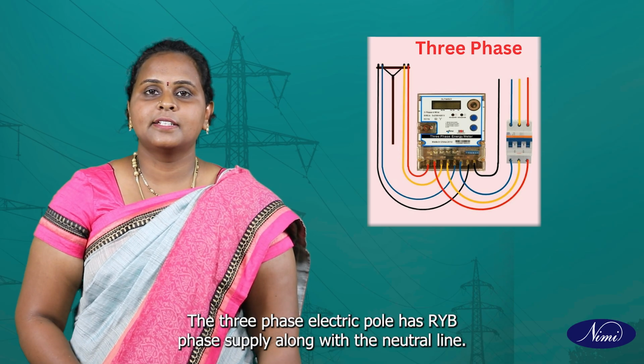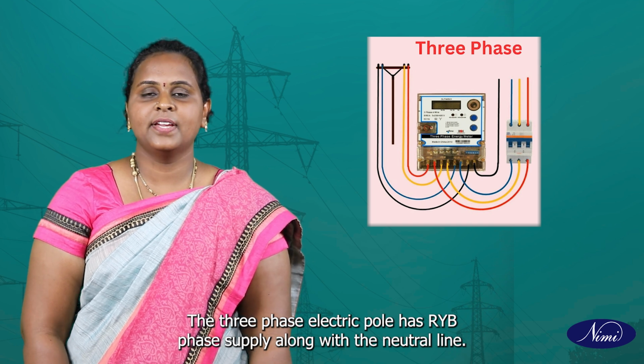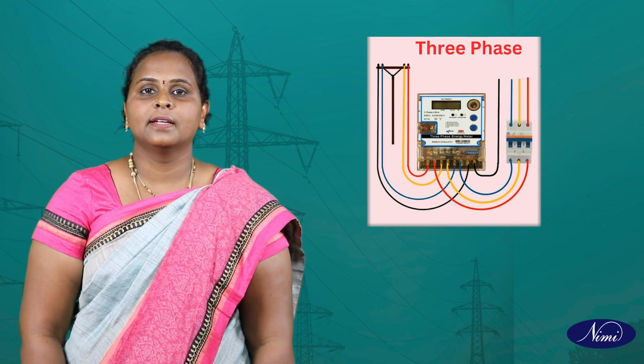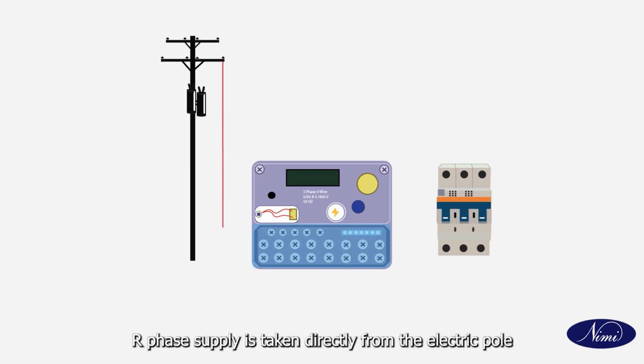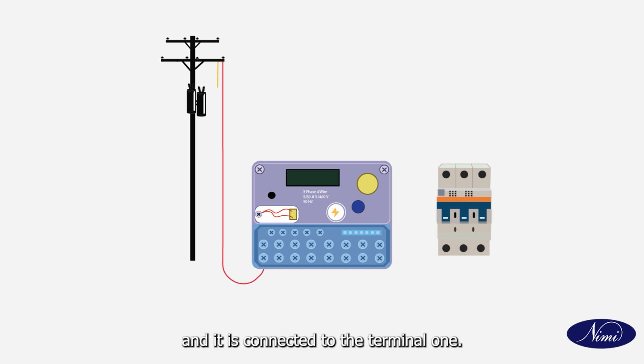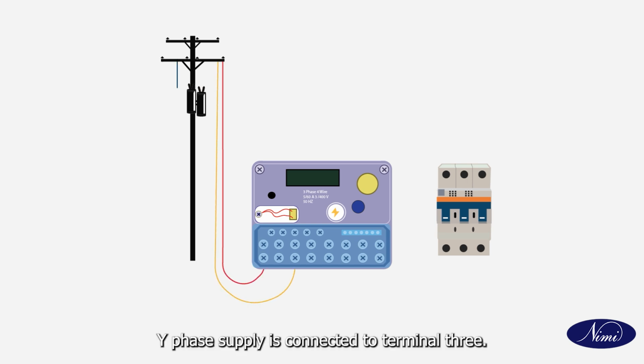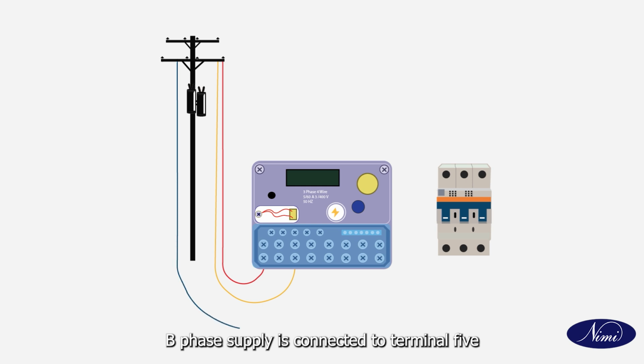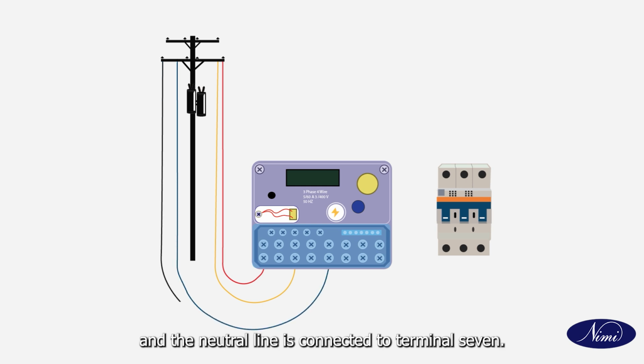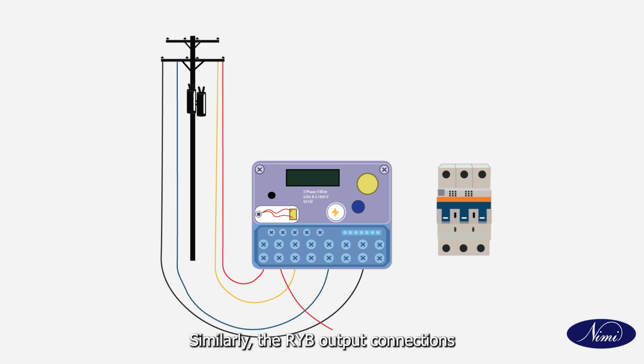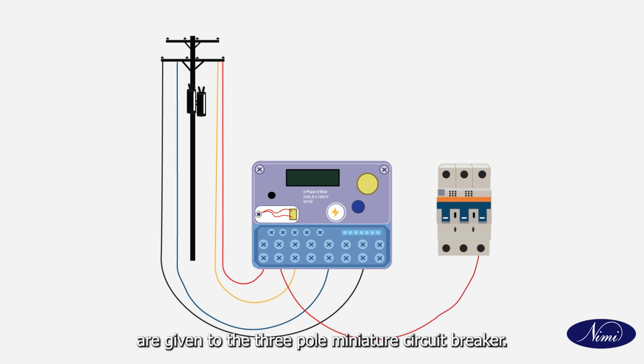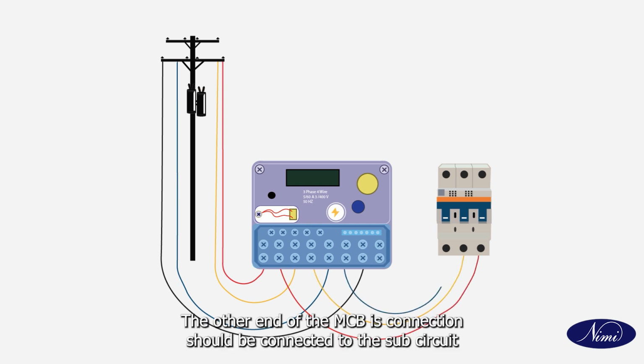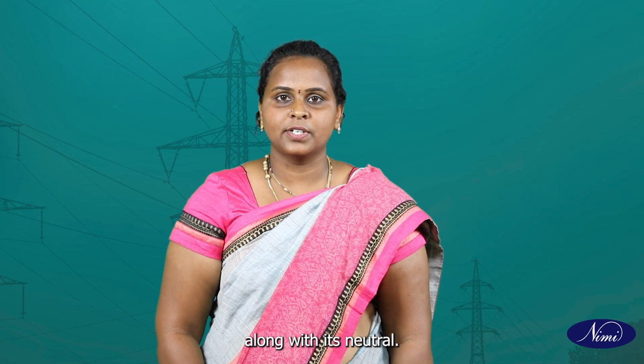The 3-phase electric pole has R, Y, B phase supply along with a neutral line. R phase supply is taken directly from the electric pole and it is connected to terminal 1. Y phase supply is connected to terminal 3. B phase supply is connected to terminal 5 and the neutral line is connected to terminal 7. Similarly, the RYB output connections are given to the 3-pole miniature circuit breaker. The other end of the MCB's connection should be connected to the sub-circuit along with its neutral.